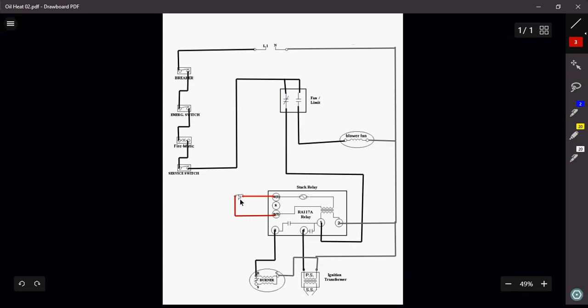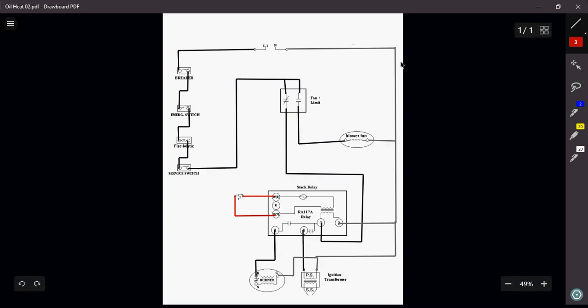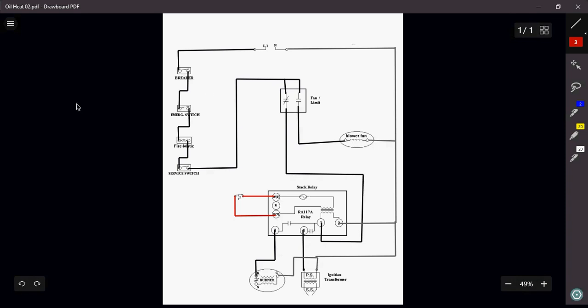Once the thermostat is satisfied, that opens, which will de-energize the coil, opening my contacts, shutting off my burner sequence. Once my furnace cools down to probably around about 100 degrees or so, that switch will now open, shutting off my blower. And that is really, ultimately, how the sequence of operation of an RA-117A stack relay actually works.